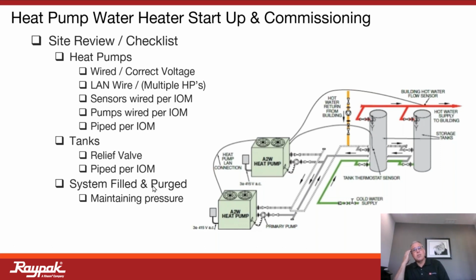In fact, I tell this story frequently. A couple of months ago, our rep in Kansas City, I was going to walk them through an X-Fire startup and commissioning, and they got there, and the breaker, the panel, was locked out, tagged out, and water pressure was 125 psi, which is a code violation on domestic. Anything over 80 psi on a domestic system is a code violation. So they were unable to even do a startup and commissioning on site just because of the conditions that were present at that particular time.